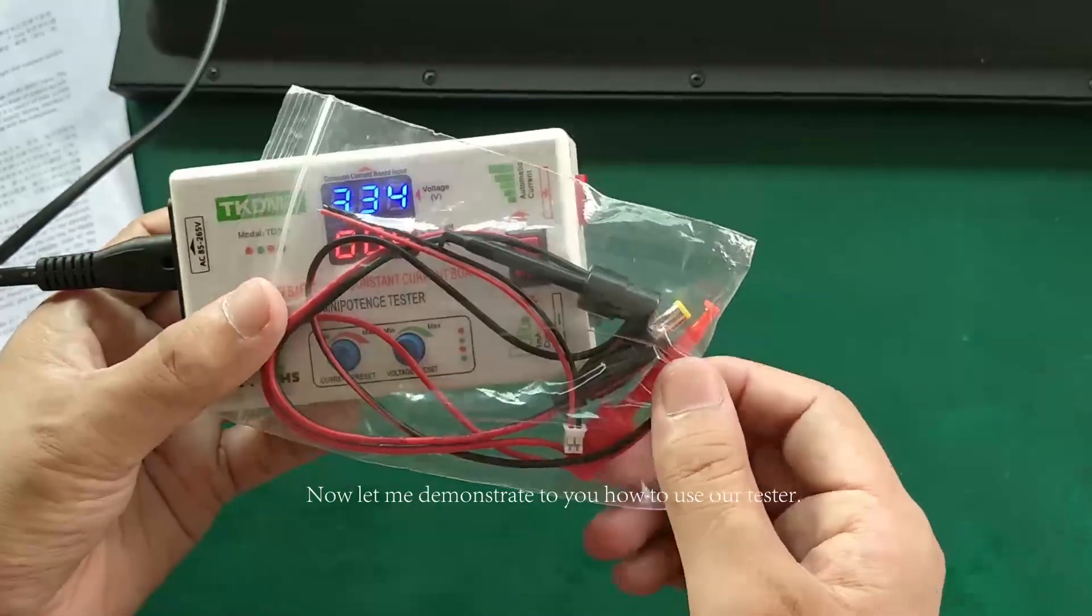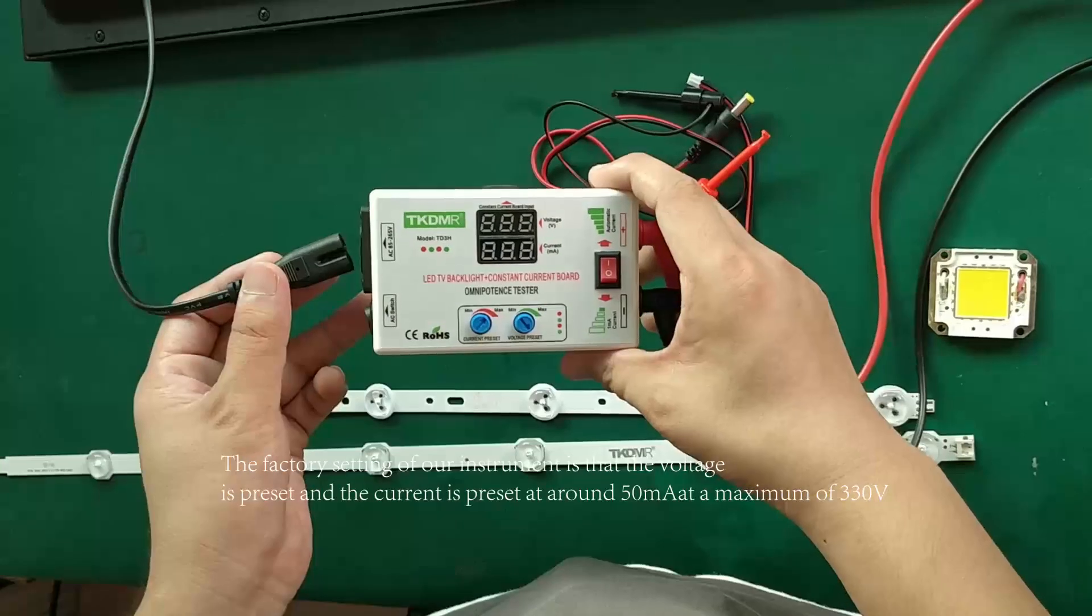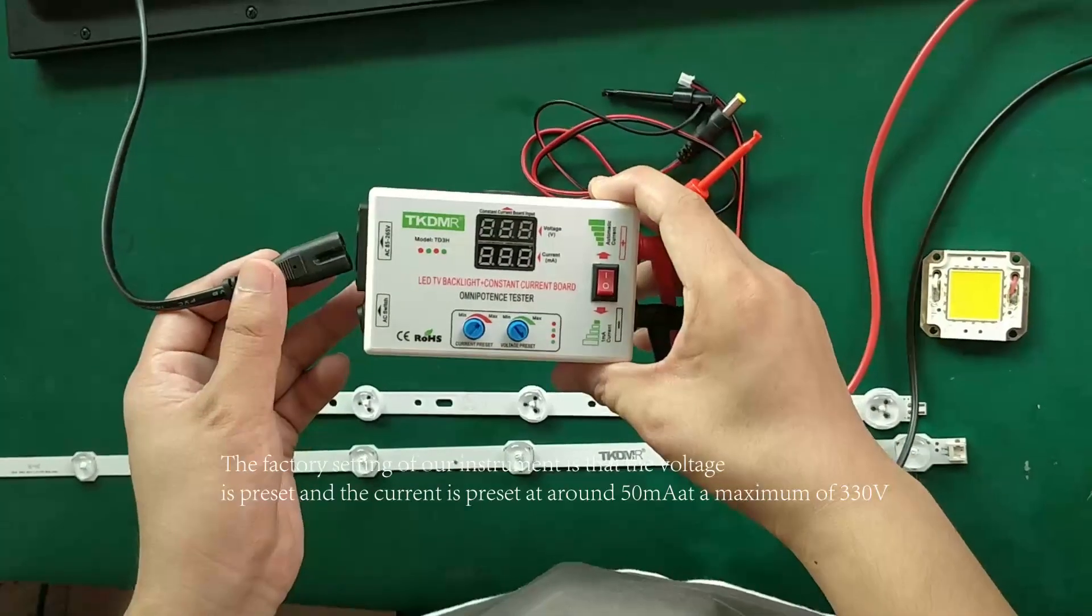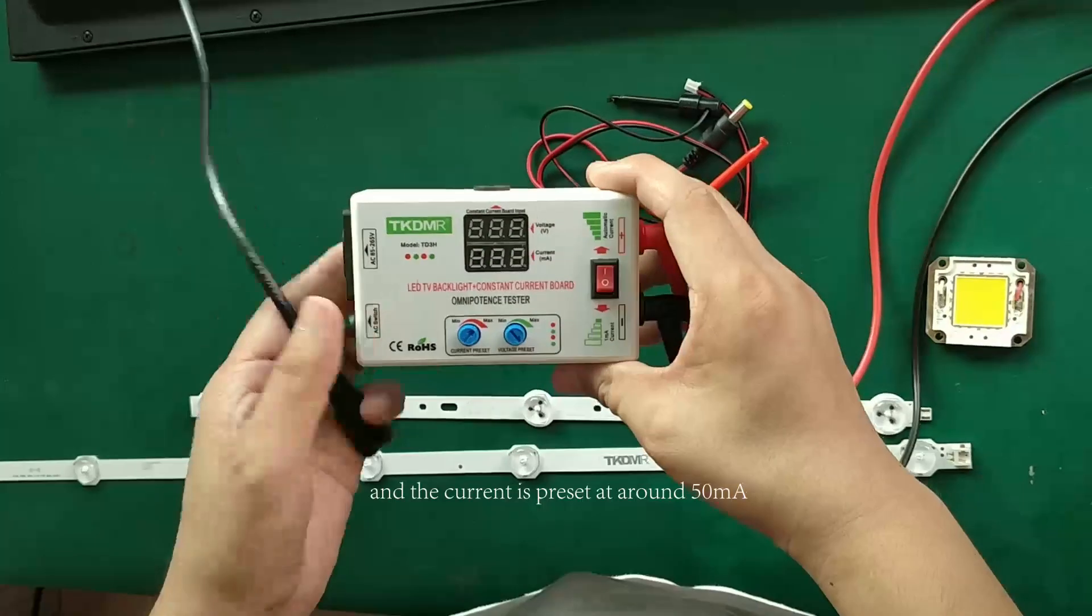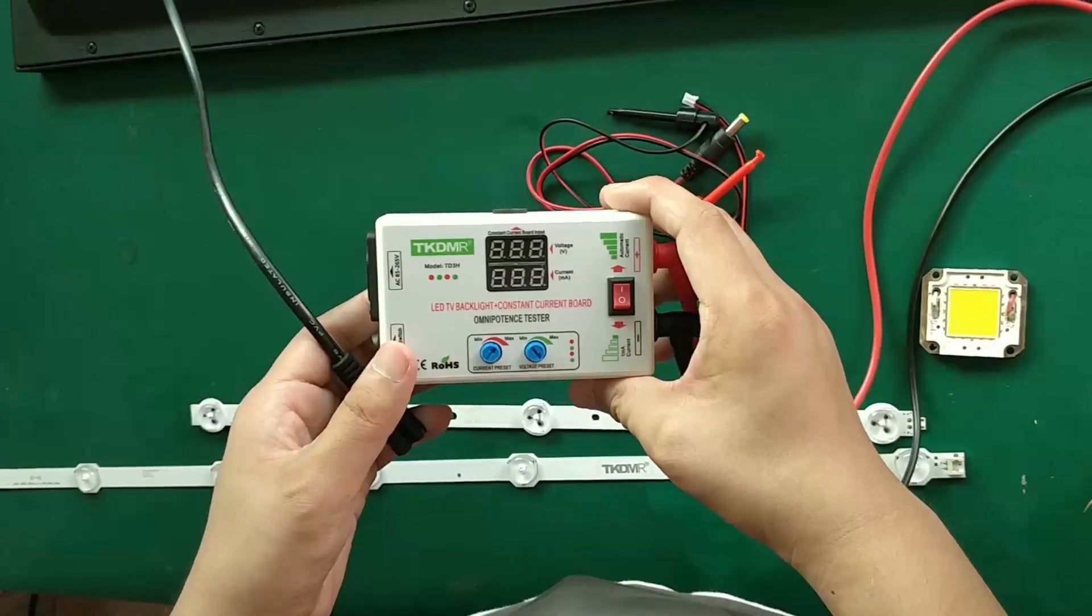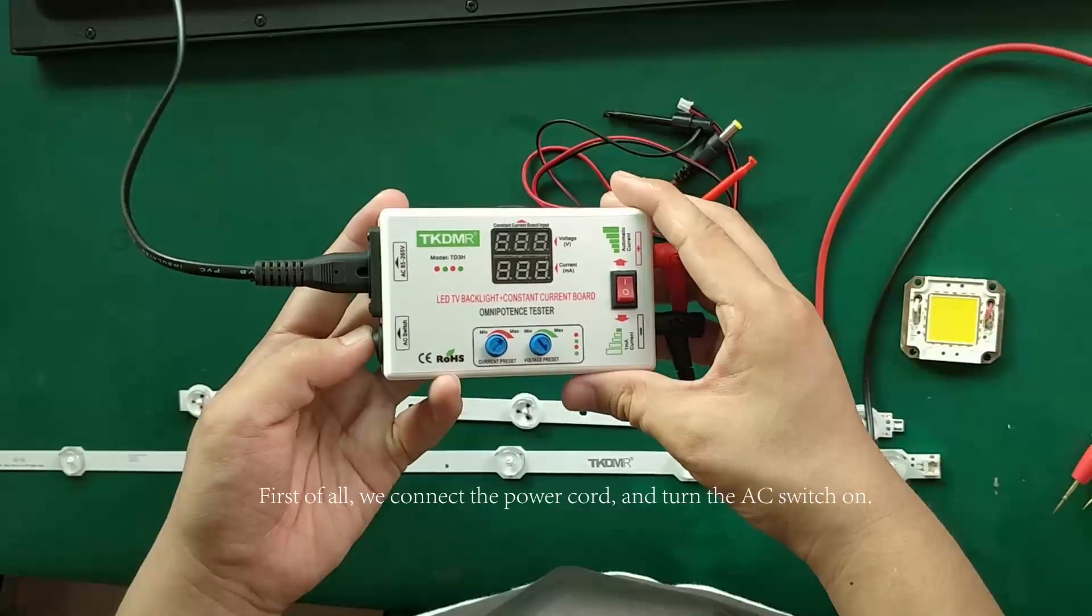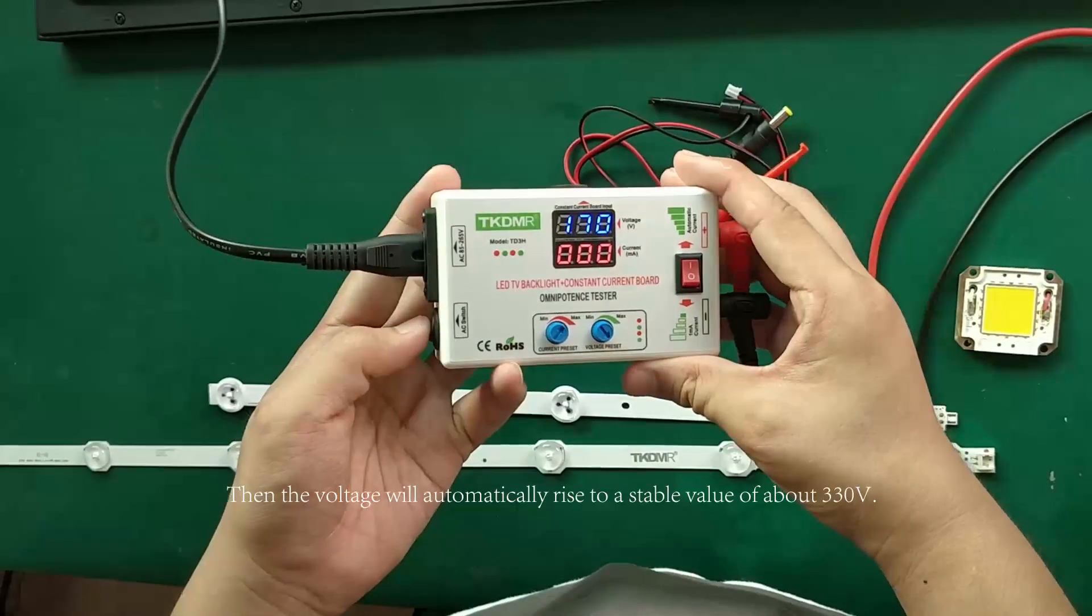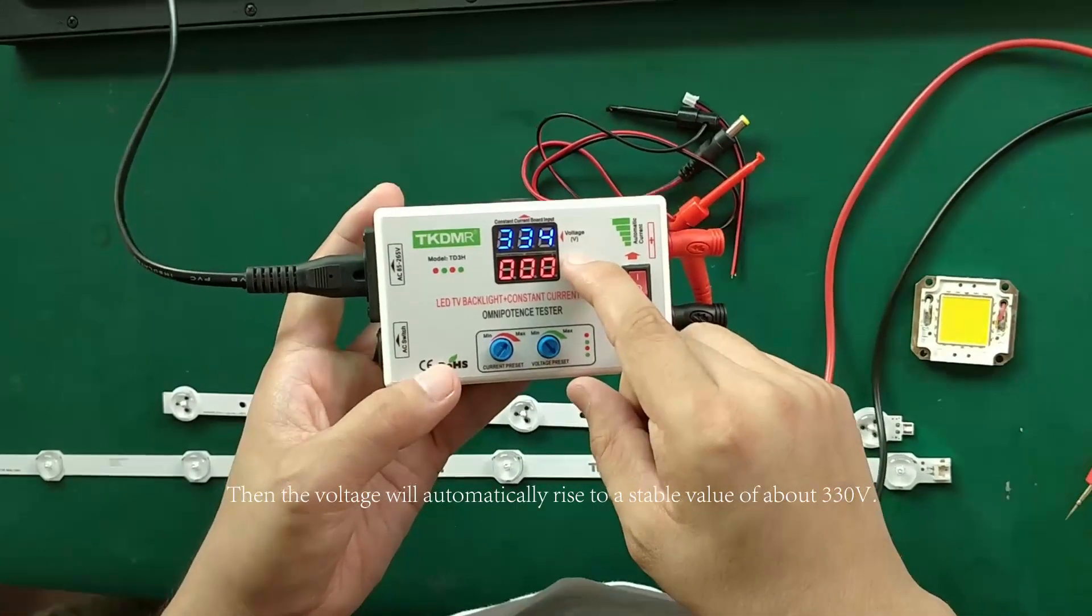Okay, now let me demonstrate to you how to use our tester. The factory setting of our instrument is that the voltage is preset at a maximum of 330 and the current is preset at around 50 milliampere. First of all, we connect the power cord and turn the AC switch on. Then the voltage will automatically rise to a stable value of about 330.